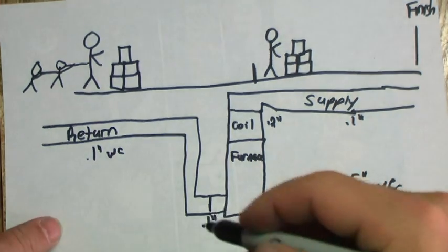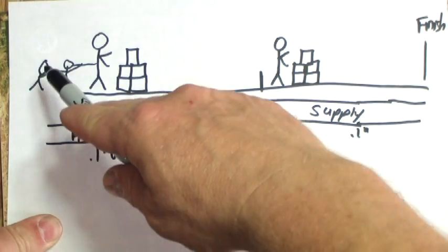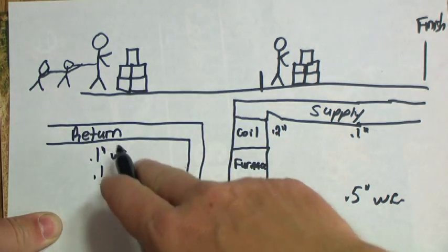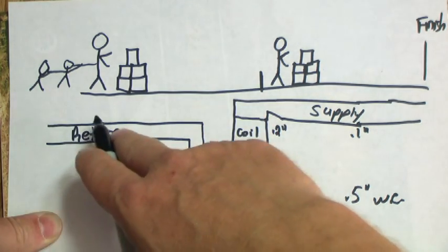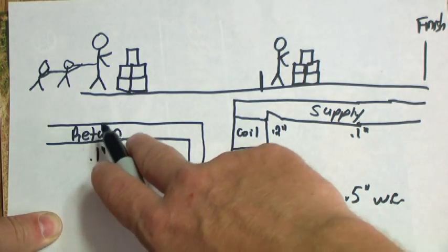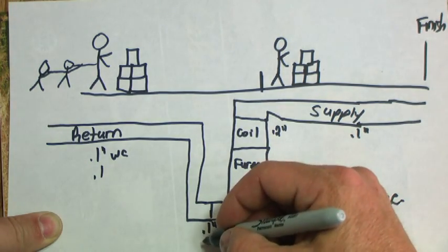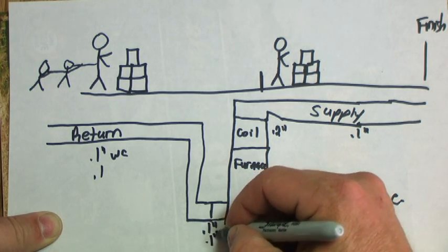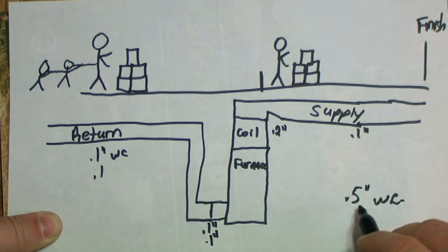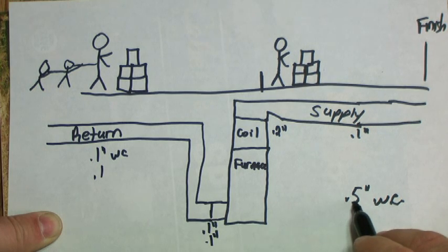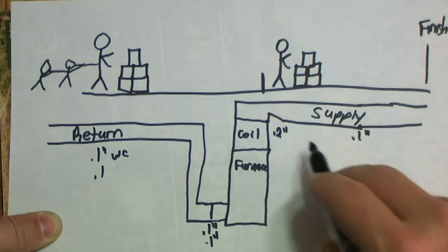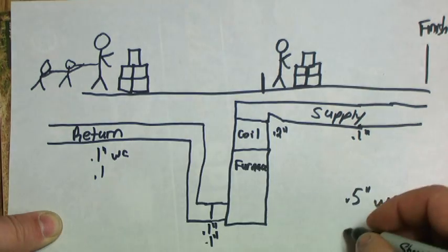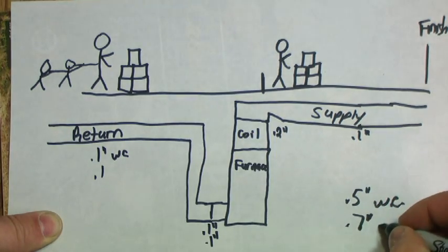Now, if we start adding resistance, just like we did in our race up here, if I add 0.1 inch in the return air duct, whether it be the registers or the takeoffs or an extra elbow, whatever the case may be, and we use a thicker filter, we add another 0.1 inch here, we're going to add that to the bottom line. So now where we had two, three, four, five, now we're going to have to add the other two, six, seven. So now we're up to 0.7 inches water column.